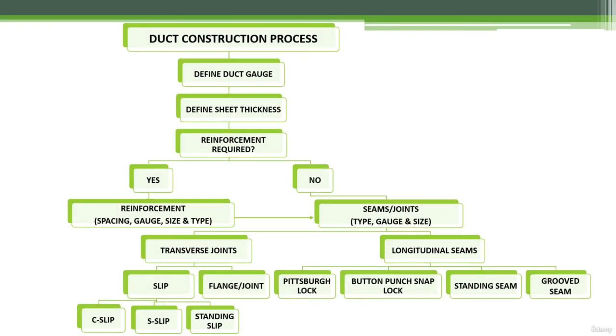This figure from SMACNA duct construction standards summarizes the entire process and shows how everything is interconnected. You start with duct gauge, specify sheet metal thickness and pressure gauge, check if reinforcement is required, check reinforcement spacing requirements, and finally specify the type and specifications of the joints and seams. At that point, you have completed the duct construction process in accordance with SMACNA.